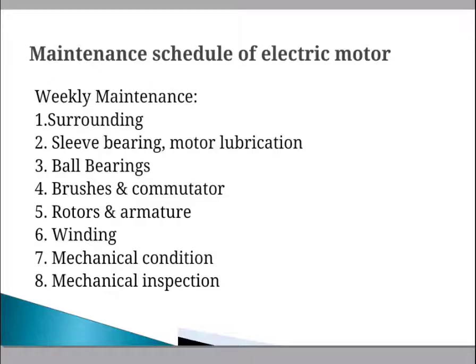Then you have to check the sleeve bearings and motor lubrication. The level of oil should be checked with the oil gauge. If the level is low, then we have to add oil or grease into the motor. Check the bearing housing; if dry, then oil them. Creeping of oil along the shaft towards the winding should be avoided in order to protect the insulation properties of the insulator present in the motor.